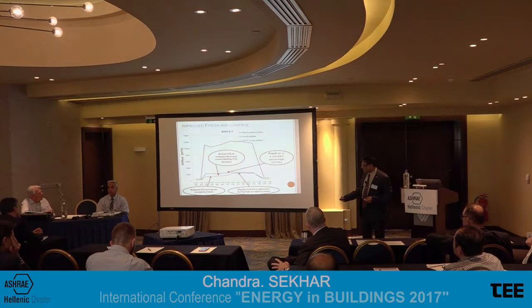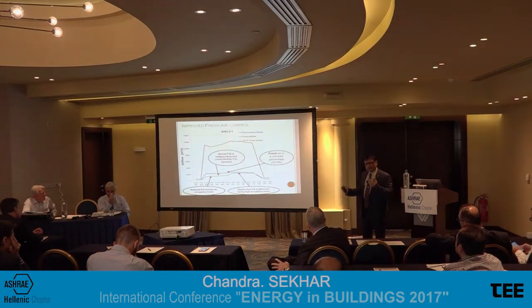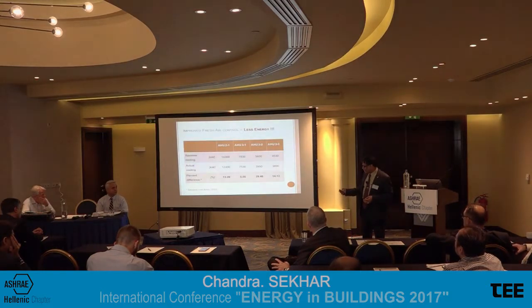Notice in this part of the day, when occupancy was low, the system used less ventilation airflow. When occupancy picked up, it went up, and then came down, following the conventional trend. So we were able to increase ventilation when you need it, and reduce it when you do not, and that translated into energy savings.